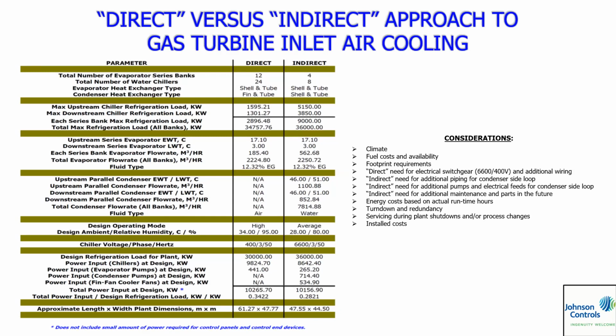So let's start looking at everything. Now let's look at capacity. Based on the air-cooled machines, we can actually dial in the capacity better. We can match the load. The actual load requirement was closer to 35, a little over 34. We were right on it on the air-cooled machines, direct. The indirect, we had to oversize just a little bit, 36. And this is in kW, but if you convert it, you're getting close to the 10,000 range. Temperatures, we're in Celsius here.